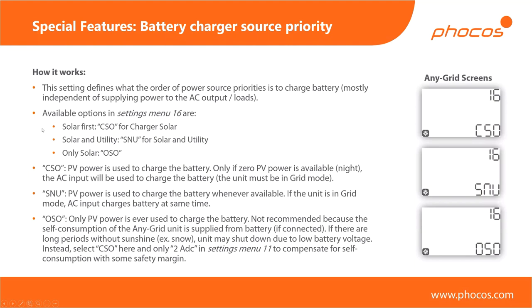There are three options for battery charger source priority. The first is Solar First: if solar energy is available, regardless of how much, it will be used to charge the battery. Once the sun sets, or if there is snow on the PV array and no solar energy at all, utility will be used to charge the battery. You can set how much current to take from utility for charging — for example, only 10 amps from utility but up to 80 amps when the sun is shining.